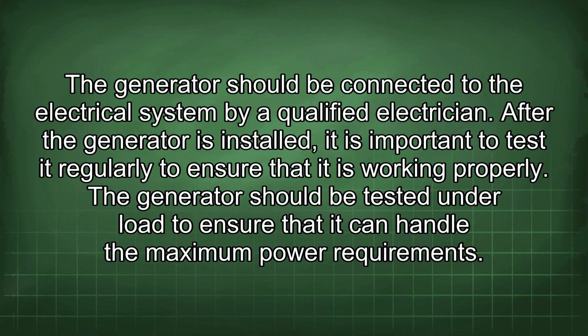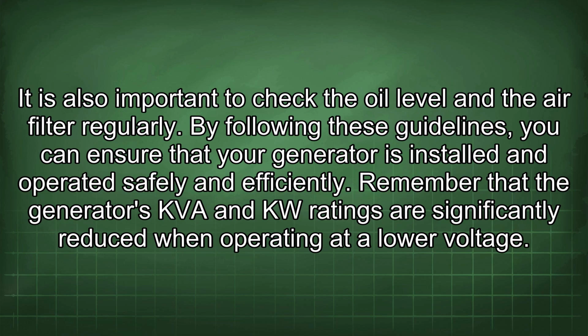After the generator is installed, it is important to test it regularly to ensure that it is working properly. The generator should be tested under a load to ensure that it can handle the maximum power requirements. It is also important to check the oil level and the air filter regularly. By following these guidelines, you can ensure that your generator is installed and operated safely and efficiently.